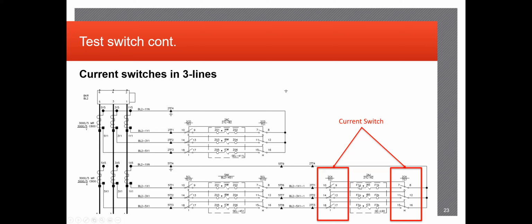The same thing too, if these points are swapped on the relay, that's going to read current going 180 degrees out from where it's supposed to be measured, which is going to be a big problem, especially when you go to energize and the client's reading currents that are just way out of whack. So being able to identify these prior to, and coming up with a good plan for taking your measurements, wiring checks, functionals, et cetera, is very important, especially before you even start the project.